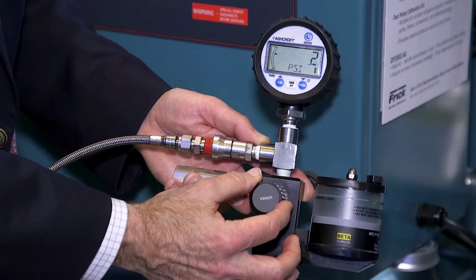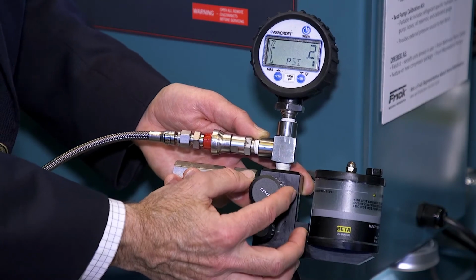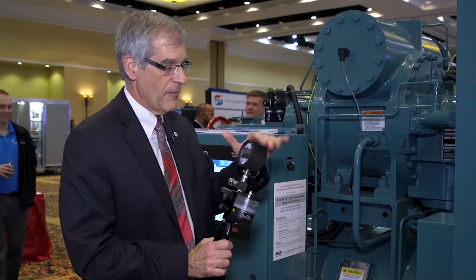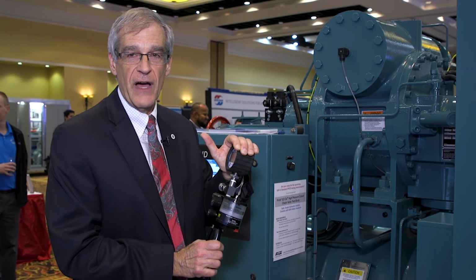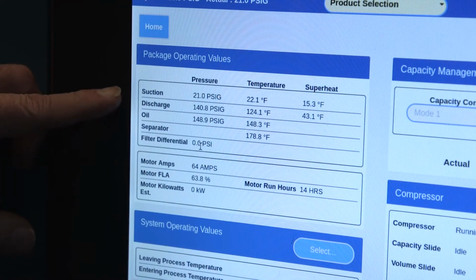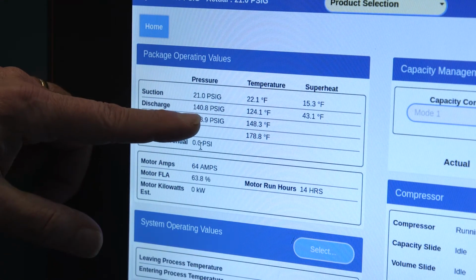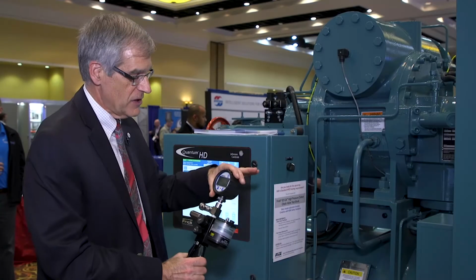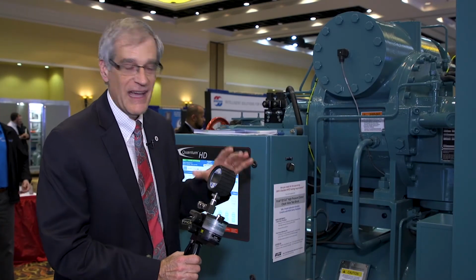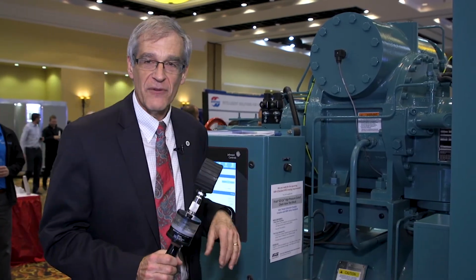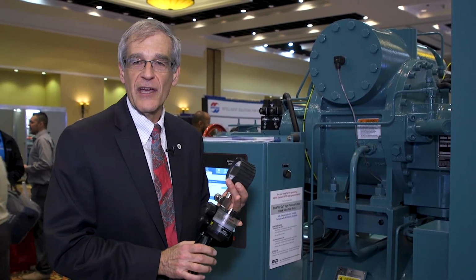And there's actually a vernier on the pump that will take about the last 5 psi. And as my gauge says I'm approaching 225 psi, I better see the machine cut out. So I'm comparing the reading on my control panel to my reading on my calibrated gauge. Once I demonstrate that it cuts out, I document it for my PSM records, and I'm ready to go for another year.